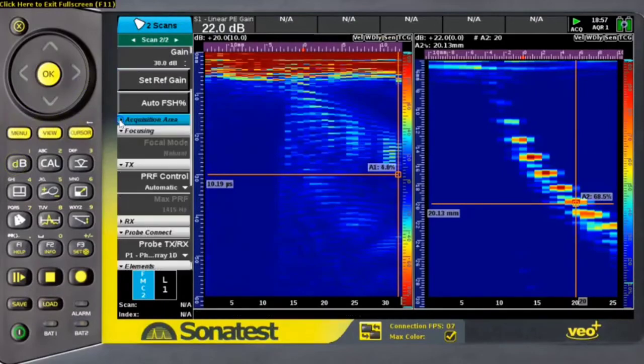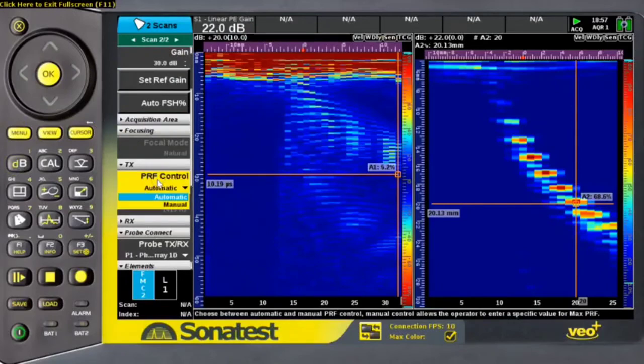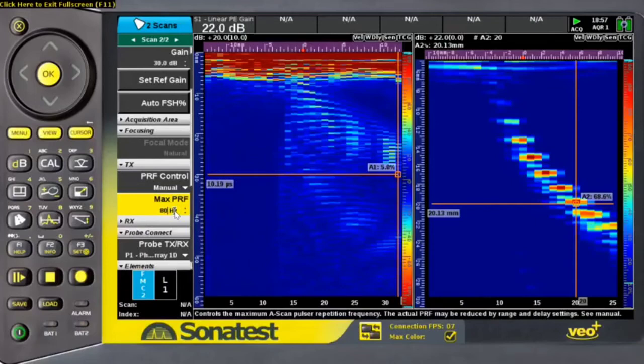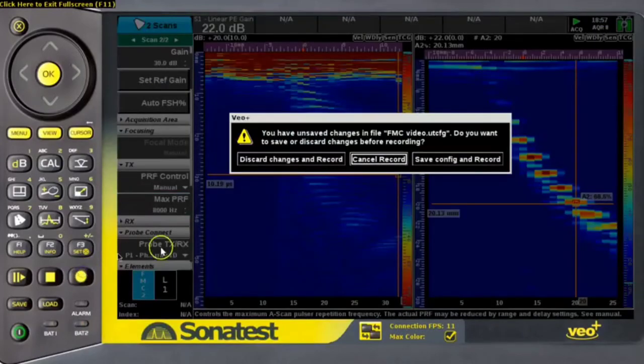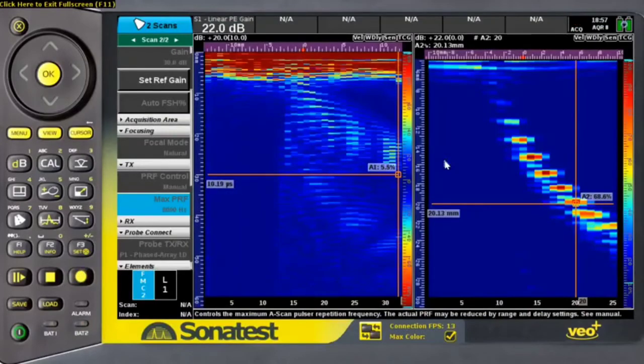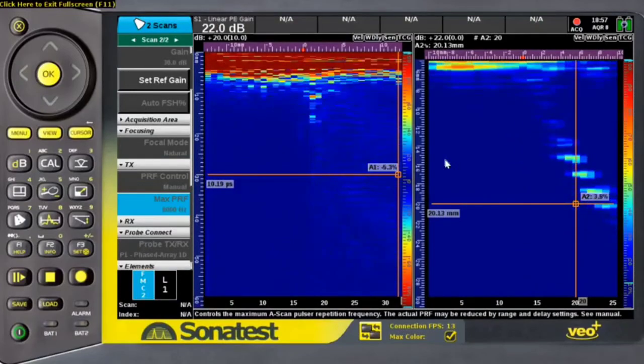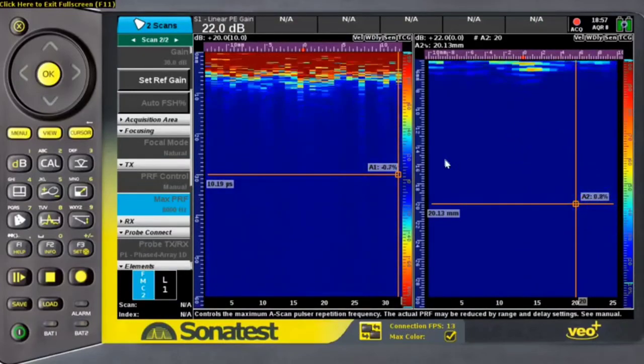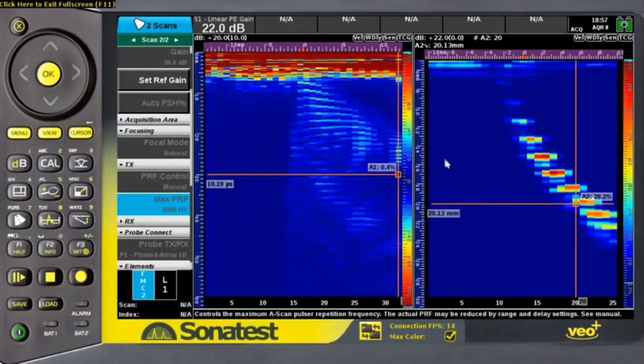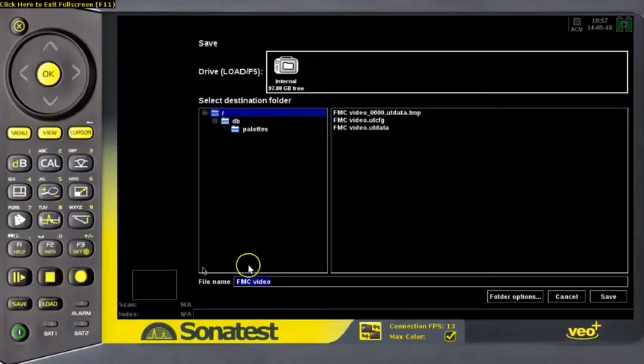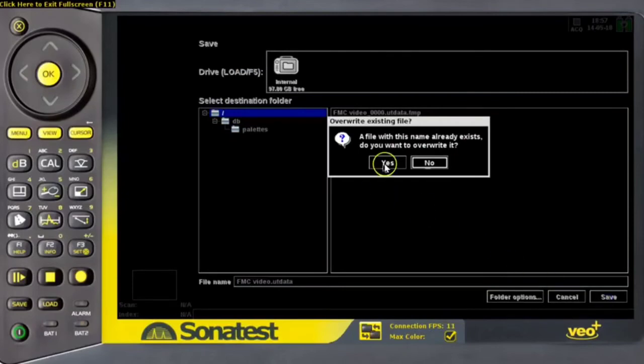Using a similar dB or gain, we can see that the FMC scan doesn't give much information like a phase array scan. However, with few manipulations to increase the speed, I will be able to record that scan on my instrument. Now what I'm doing is I'm recording over time, but I could also record using an encoder. As we can see, I moved my probe over the defect, and now I can save the information on my VEO Plus instrument memory.